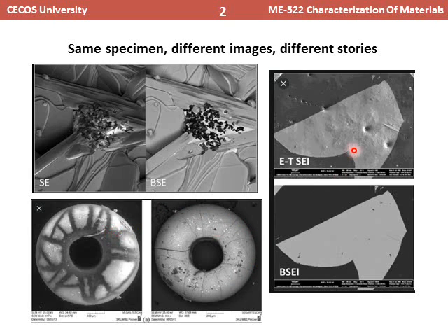The third images, the couple of images, are on the right hand side. There are two images, top and bottom. The top shows the secondary electron image of an object, and the bottom shows the image formation of backscattered electron of the very same object. In the secondary electron image formation, you can easily see the contours of the surface.